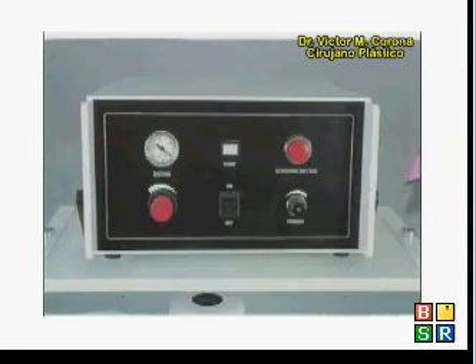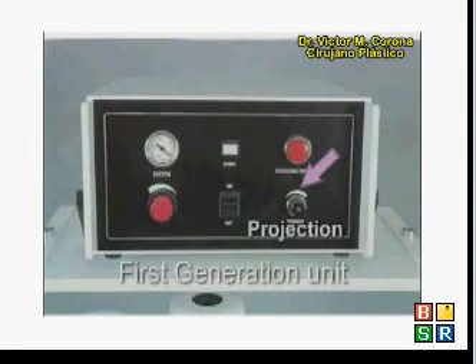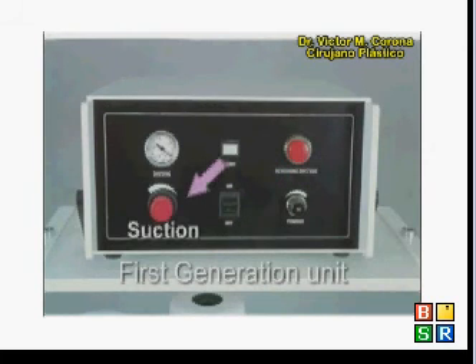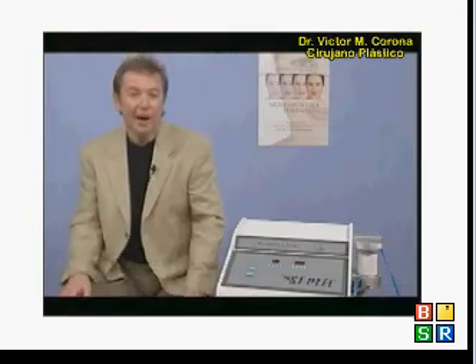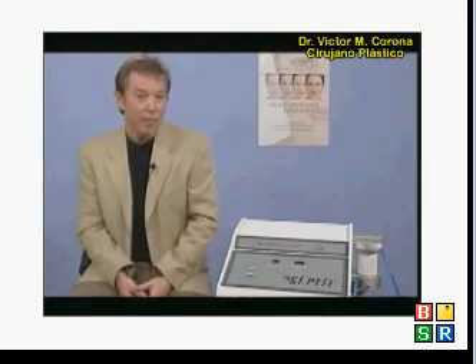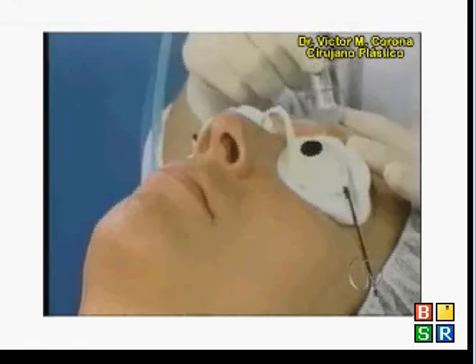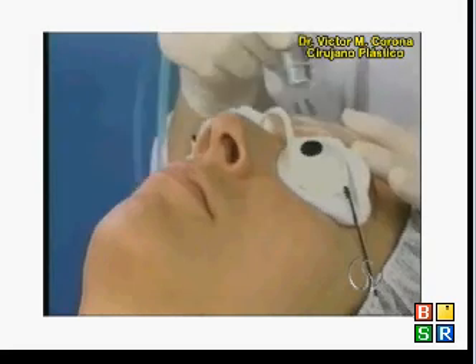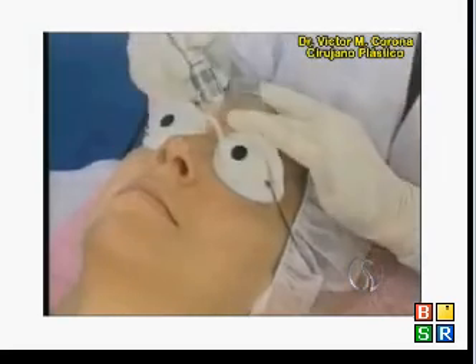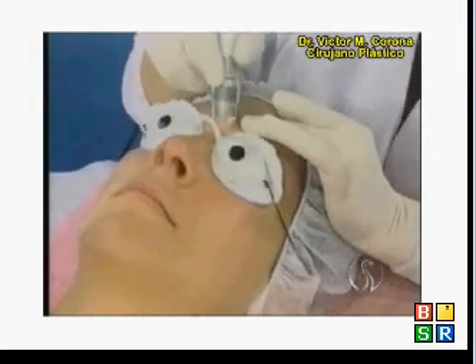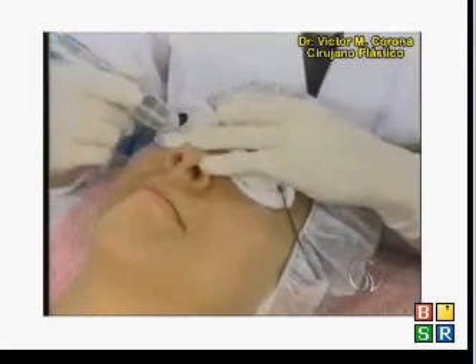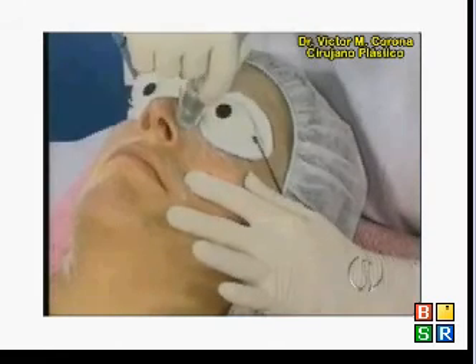The old two-button calibration system, one for the suction and the other for projection, means that you constantly need to adjust the controls, trying to find the right calibration for the area that you're working on. But the skin doesn't have the same thickness everywhere. A completely different calibration is required for the forehead, where the skin is thicker, for the eye contour, which is very thin, and for the nose. The result is that most of the time you have too many crystals or not enough, too much vacuum or not enough.